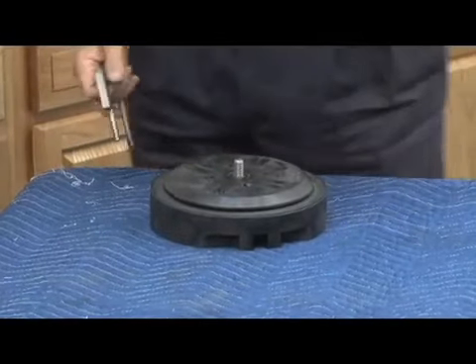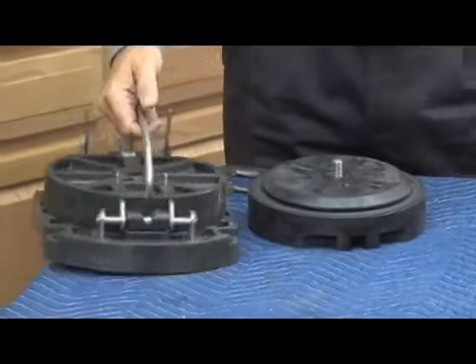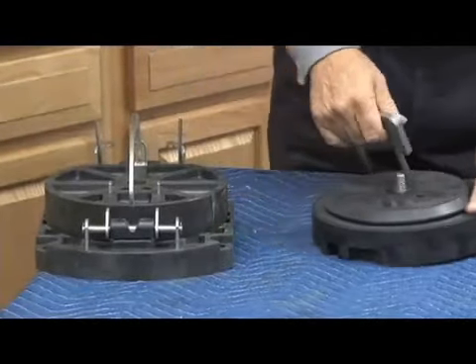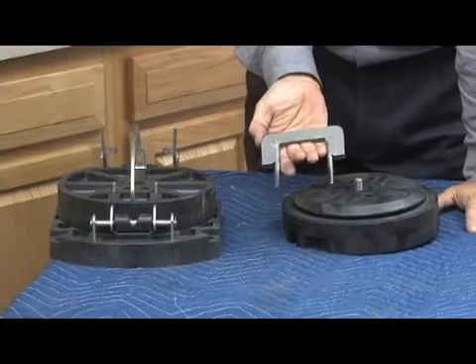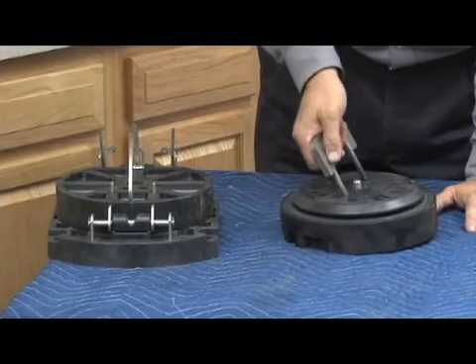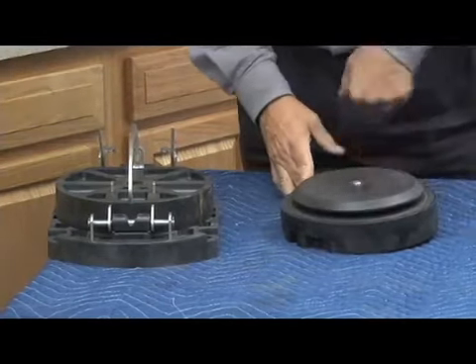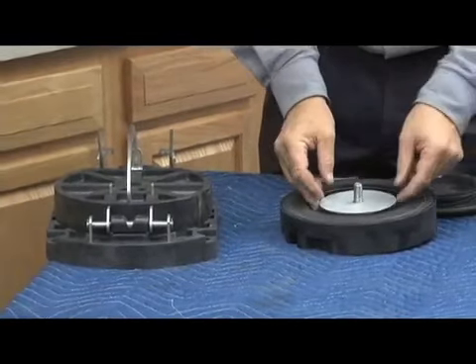When we're talking about the double check, remember I had it apart and I said all I have to do is unscrew this plate. Well, here's that plate, and I'm going to show you this one so you know how it goes back on the other one. I mentioned that the retainer clip from the fabricated steel body fits right in. Now, by unscrewing that disc retainer plate, it will come out.